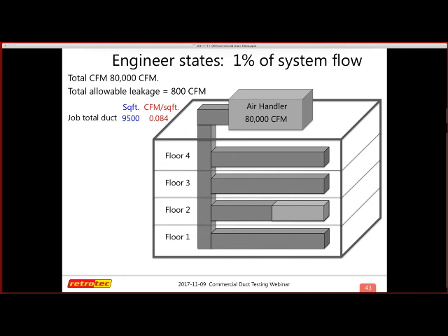The only place where we're leaking is in some fractions of strange connections, or probably at the air handler or some other place they can't actually account for. We're going to test each of these trunks by themselves in these runs, but they struggle to get down to 1%.